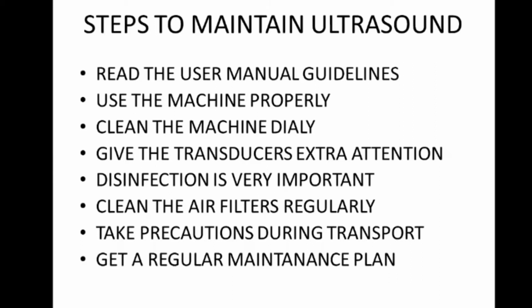If you find any scratches on the probe, you should immediately call the service engineer and ask them. And if the nylon or any wire comes out, you should not use cellophane tape or any type of tape to fix it and use it. You should not do that. You should either change the entire probe, or call the particular service engineer and ask them to change that nylon wire. Or if the rubber is coming out, you should not place sellotape on top, and you should not use the probe. You won't get a proper image if you use that.